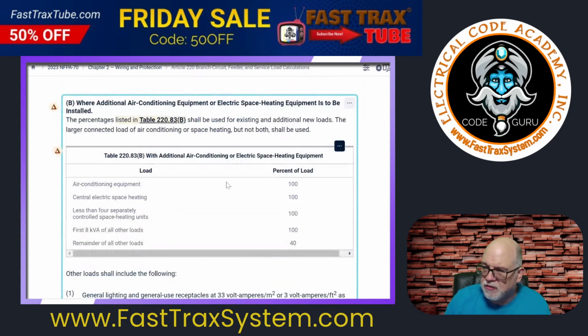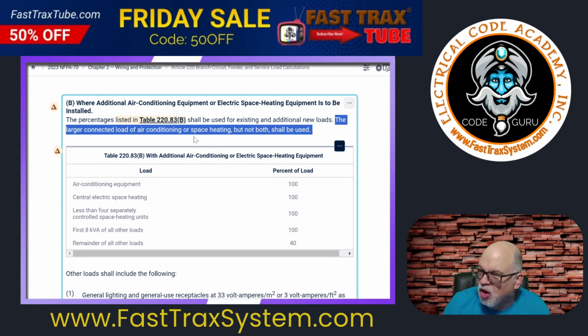So what that means is you're taking the additional air conditioning or heating or the separately controlled space heating all at 100%. But you're only taking the larger of those, okay? So that's what it tells you up here, right? It says the larger connected load of air conditioning or space heating, but not both, shall be used.